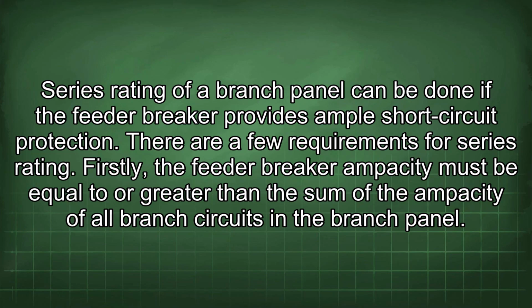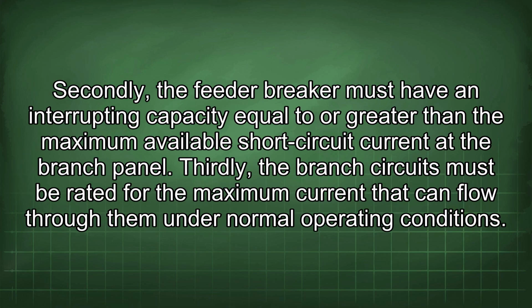Series rating of a branch panel can be done if the feeder breaker provides ample short-circuit protection. There are a few requirements for series rating. Firstly, the feeder breaker ampacity must be equal to or greater than the sum of the ampacity of all branch circuits in the branch panel. Secondly, the feeder breaker must have an interrupting capacity equal to or greater than the maximum available short-circuit current at the branch panel.